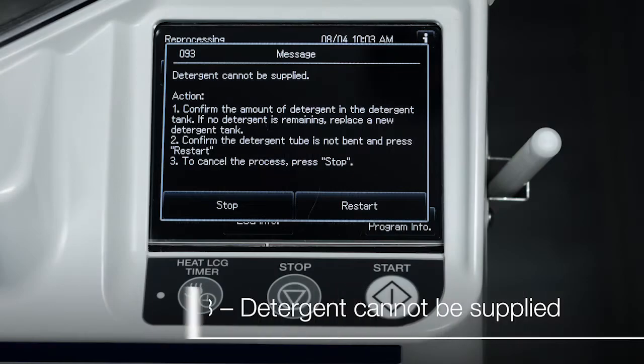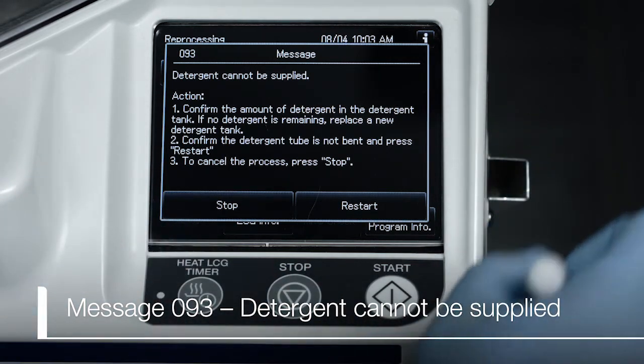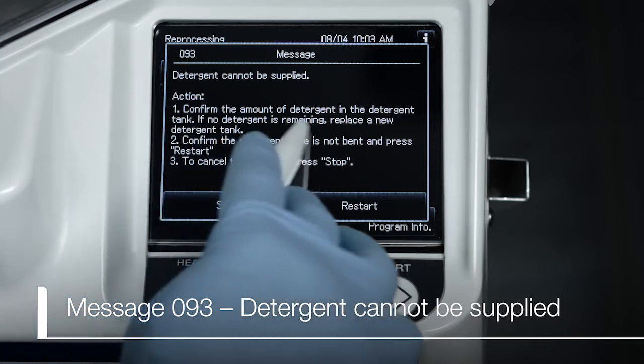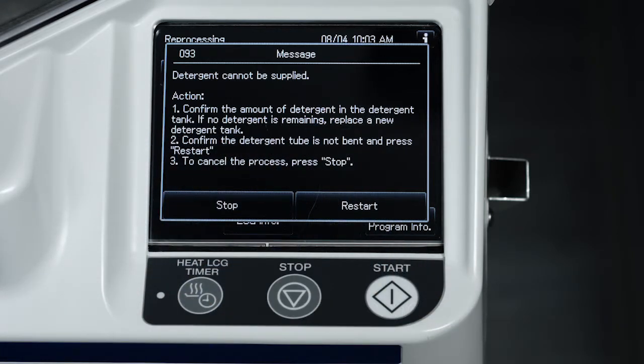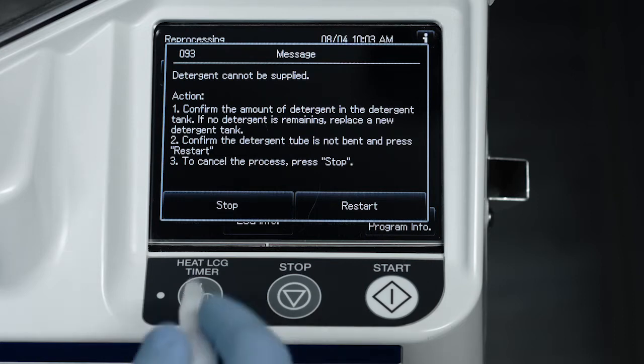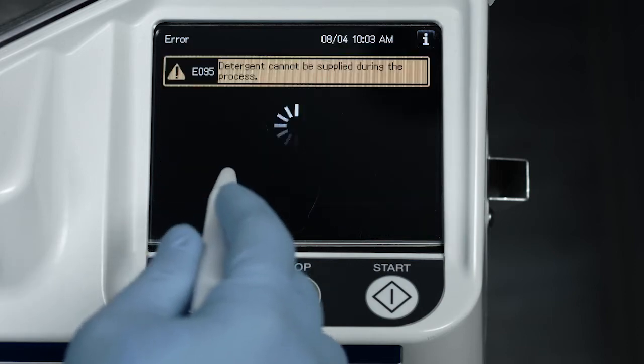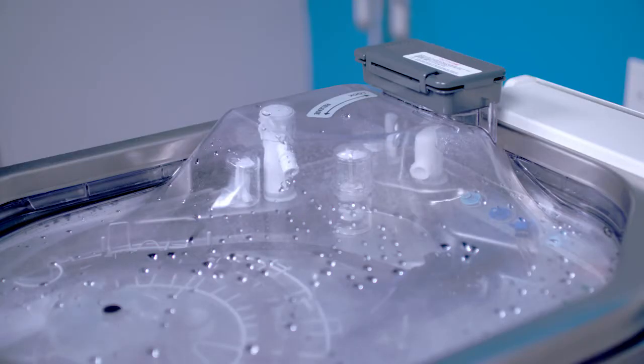The OER-Elite will display a 093 message advising the user to confirm the amount of detergent in the tank and check tubes. If the message 093 reoccurs after confirming the detergent volume is sufficient and the tubing is in good working order, simply press the stop button and proceed with remedial action.